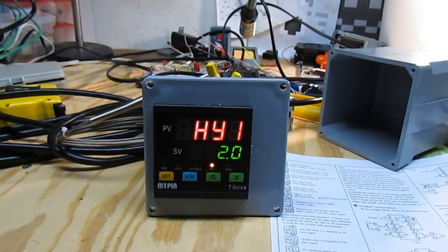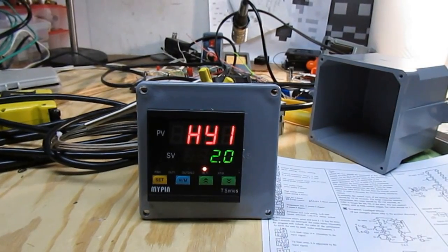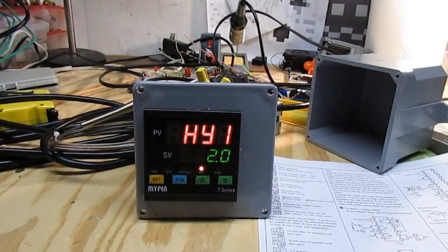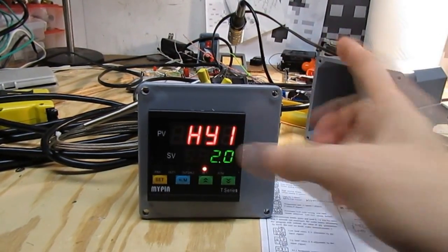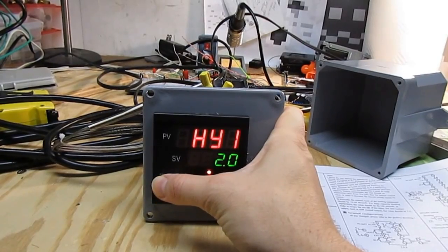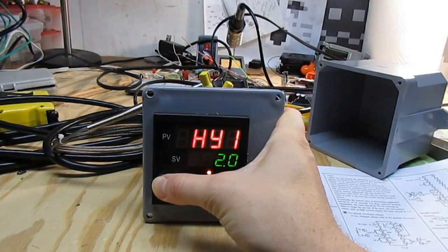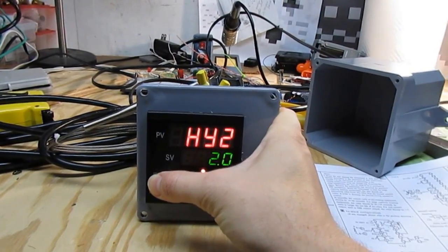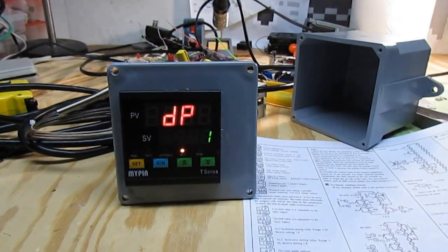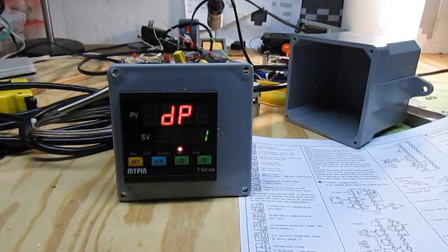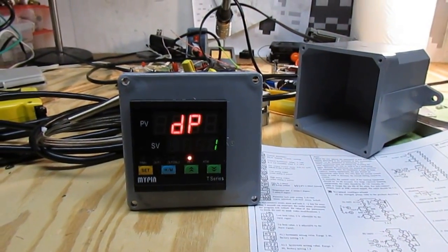This is the setting where you tell it how close to the target temperature you want it to keep before it kicks on the cooling. So this is set to 2 degrees. So if it goes 2 degrees high of my target temperature, it'll kick on the compressor. And I set both of those to 2. One of them's for alarm 1, one of them's for alarm 2.